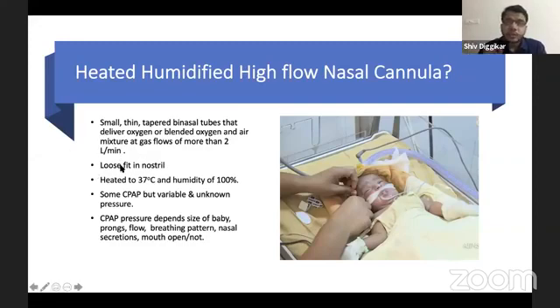Some studies have even used more than 1 liter per minute, but the standard definition is 2 or more than 2 liters per minute. They fit in the nostrils, but they fit very loose. This is the most important: the primary success of HFNC depends upon heating it to 37 degrees Celsius and humidifying it to about 100%. So humidity and heating is very, very important. That's where the name comes from: heated, humidified, high flow nasal cannula. High flow because you are giving a flow above what you can give in low flow, that is 2 liters. It gives CPAP, but it's not constant. It's a variable CPAP, and you can't measure it in HFNC. That's one of the disadvantages.